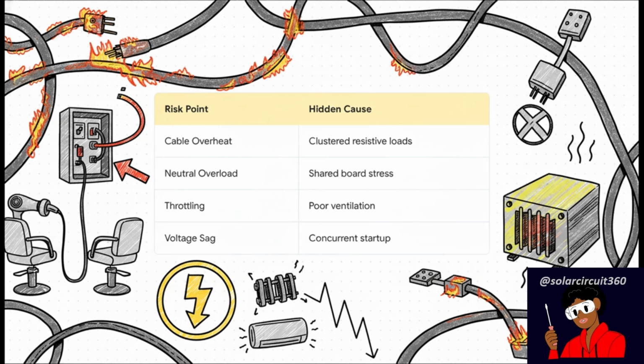shared distribution board. Third, your inverter will start throttling hard during midday peaks because, remember, an 8 kilowatt system is super unforgiving when it's stuffed into a hot, poorly ventilated utility space. And fourth, you're going to get dangerous voltage sag when heating elements and an HVAC startup hit at the exact same time. Even breakers that look rated correctly on paper will absolutely fail under sustained heat if you ignore the physical reality of the environment.